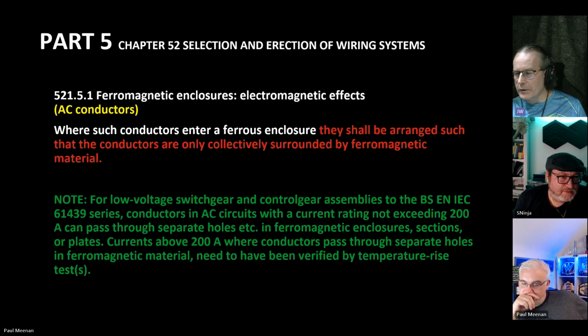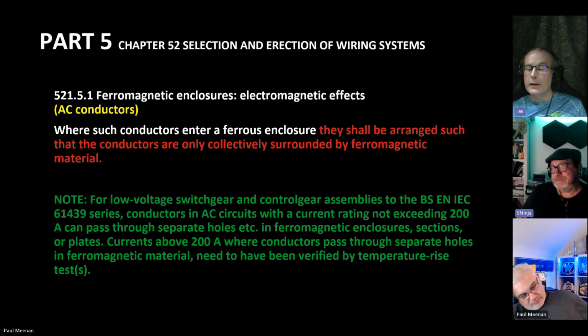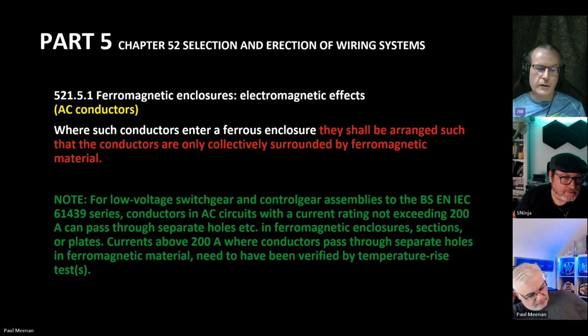And if it's only 50 hertz, it's probably going to be okay because the temperature rise is going to be fairly small. Unless, of course, there's a load of harmonics, which you're going to inevitably get on any modern installation because of all the electronic stuff that's connected, in which case the heating could be dramatically more. Unless the manufacturer has done their temperature rise test on it, in which case you can do what the manufacturer says. But the same problem applies there, that if the manufacturer's tested it at, say, 400 amps at 50 hertz, but then you stick it in a real installation and there's a load of harmonics at much higher frequencies, and it overheats and melts. So it's just asking for trouble.